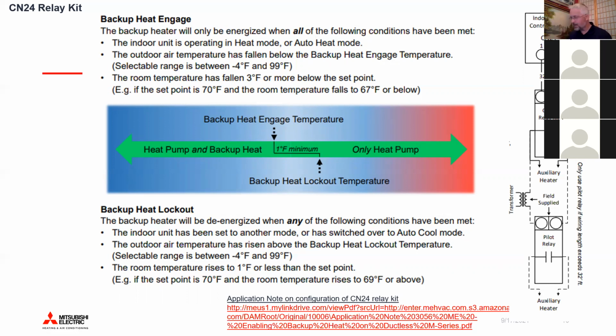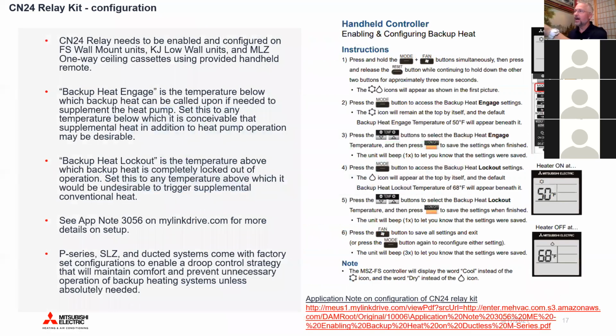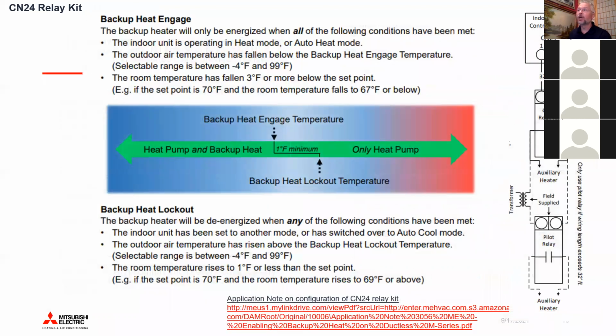And I probably should say this slide kind of goes with the next slide. So the next slide here, and I'll go back and forth a little bit on these, is a picture from, again, another app note off of my link drive that describes how to engage this and to adjust the factors. And the factors that you're adjusting are two-point temperatures. One is the backup heat engage temperature. So below this temperature, the heat pump can call for backup heat anytime it wants. And above the backup heat lockout temperature, only the heat pump will operate.